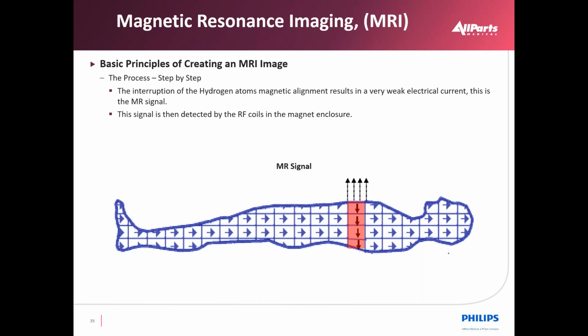There are 2 main methods to increase the MRI signal. One is to reduce the temperature to absolute zero, minus 273 degrees Celsius, so that all the nuclei align. In this state, all the spins would occupy the low energy state, but turning the patient into a popsicle wouldn't be a safe alternative. The other method for increasing signal is to increase the field strength of the magnet.